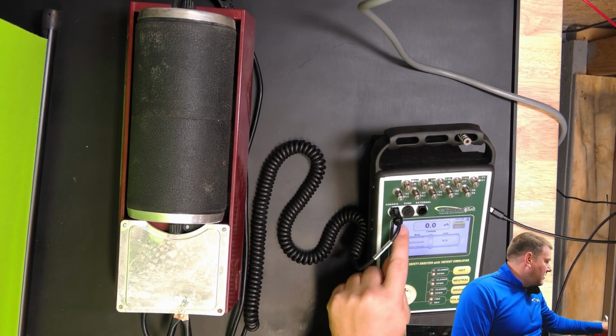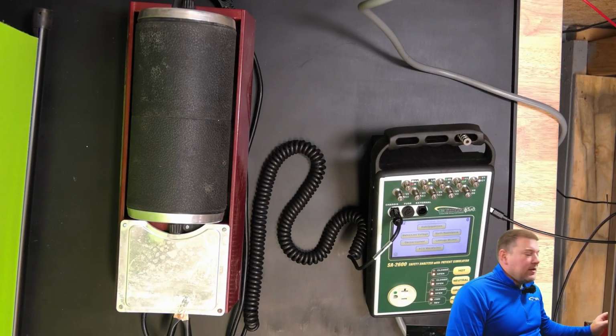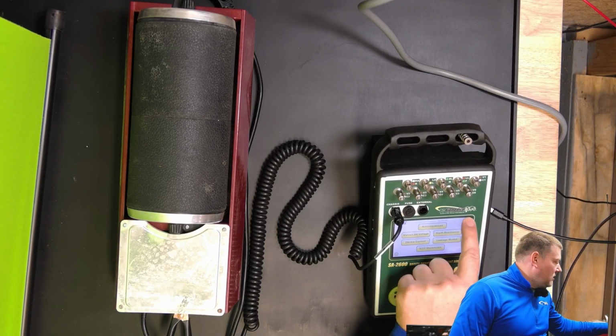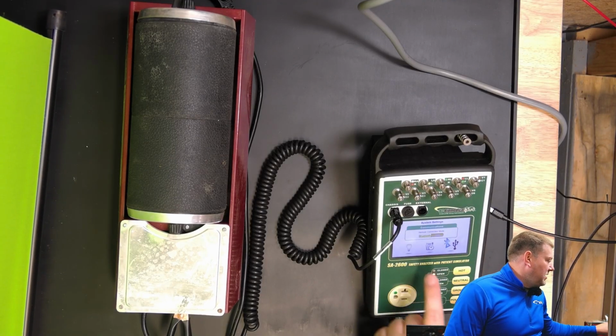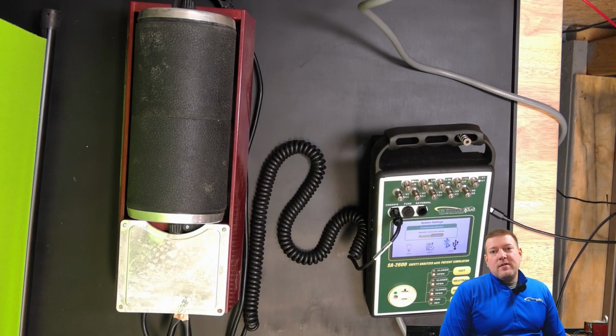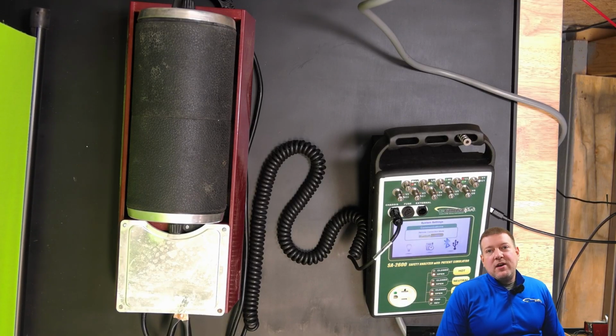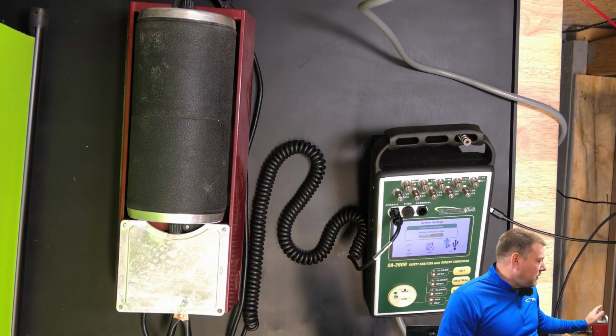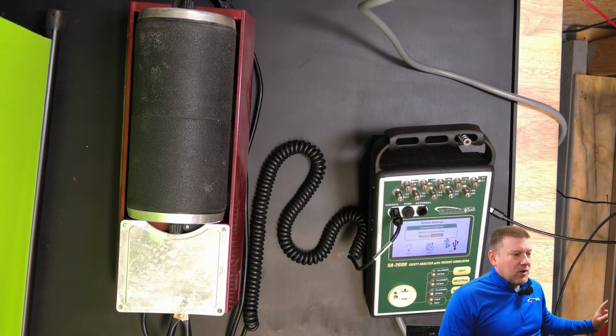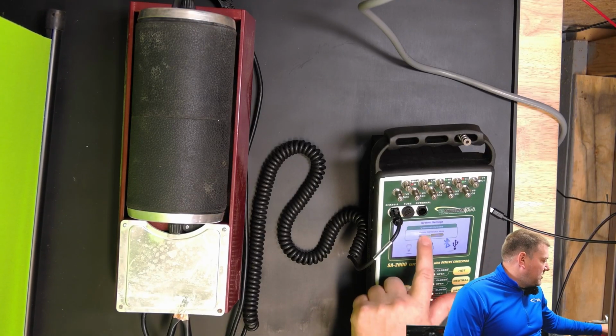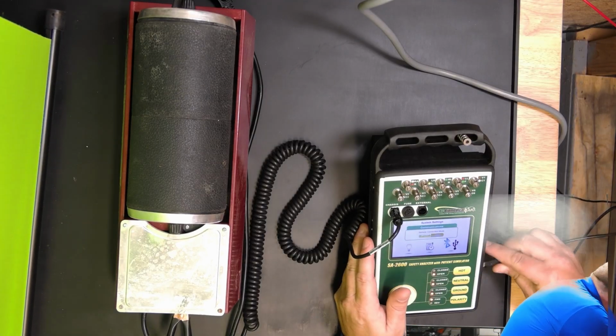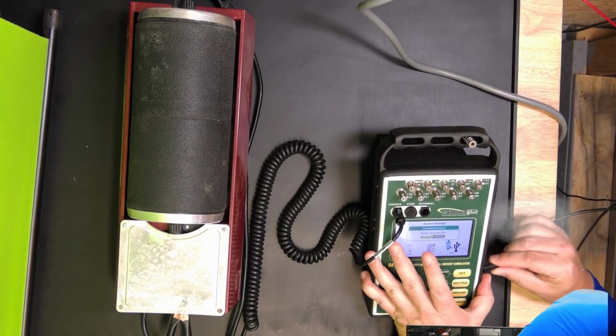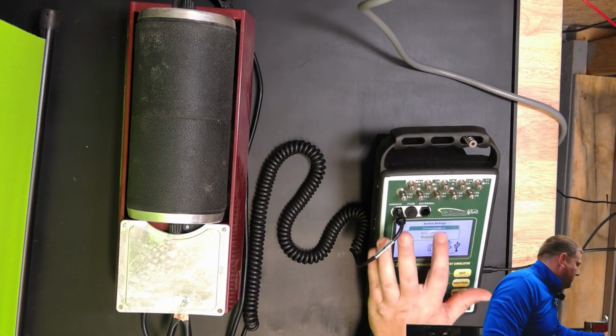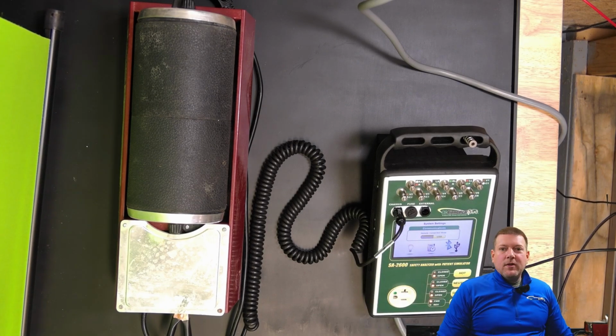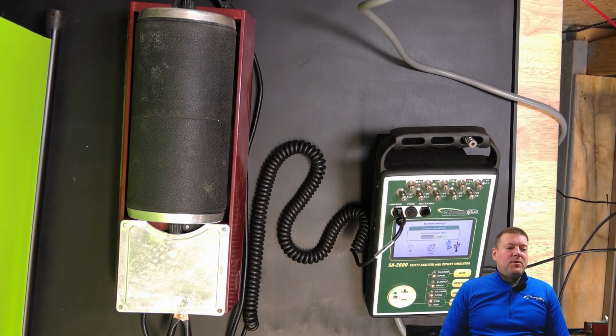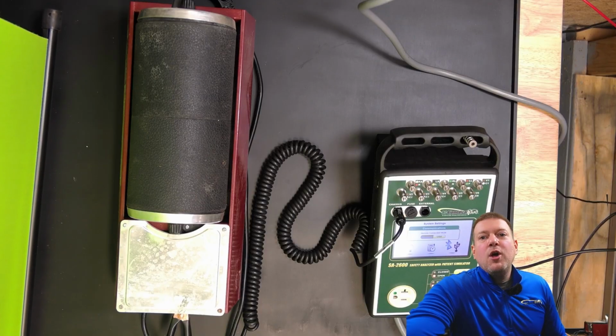Okay, and let's go ahead and back out to the main screen. Now here is where you want to check and make sure that your electrical safety meter is going to be on Bluetooth. Now we can set it to USB, and that allows us to do some other cool stuff. But if you're going to run right into testing, we're going to set it on Bluetooth. I'm going to go ahead and change it over to USB, and we're going to plug this bad boy in. There's a USB port right here on the side. A little tone is heard on the computer, and now we're going to pop over and I'm going to show you what we can do next.